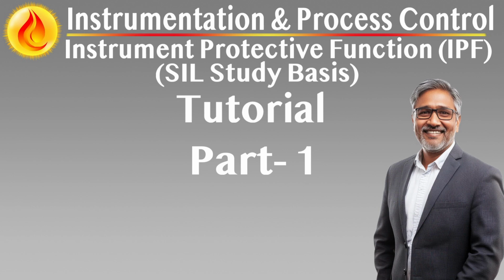All field maintenance, calibration, or modification activities affecting IPFs must be traceable, controlled, and reviewed to preserve functional integrity. Documentation and change management discipline. A complete and controlled documentation set must support each IPF, including functional description and SIL classification, verification and validation results, hardware and logic architecture, proof test procedures and intervals, change management records, bypass control protocols.